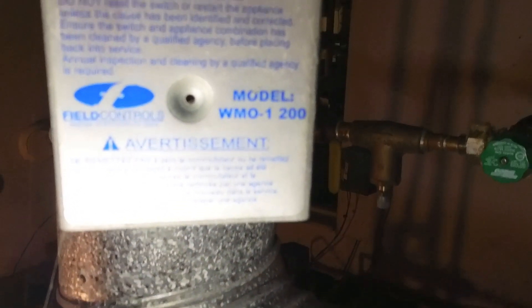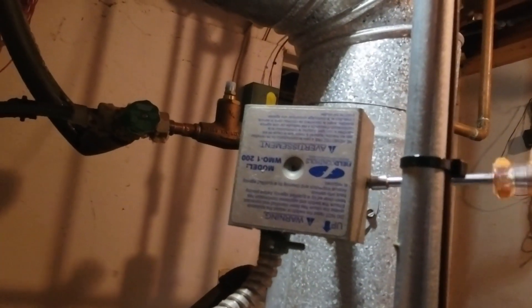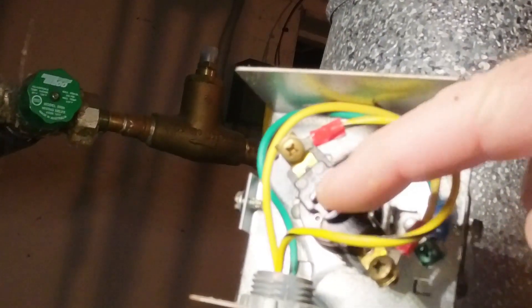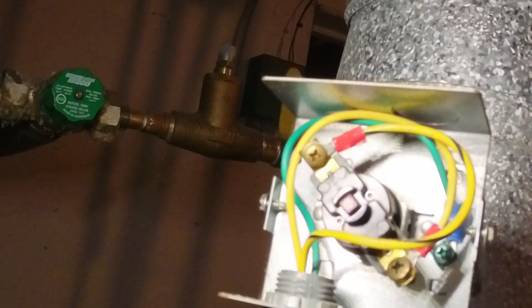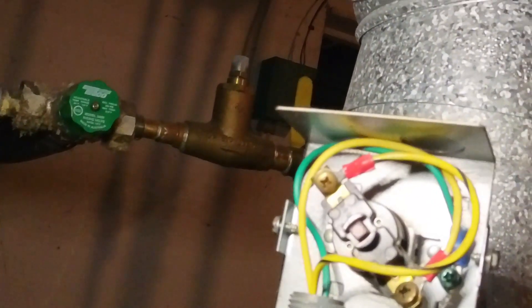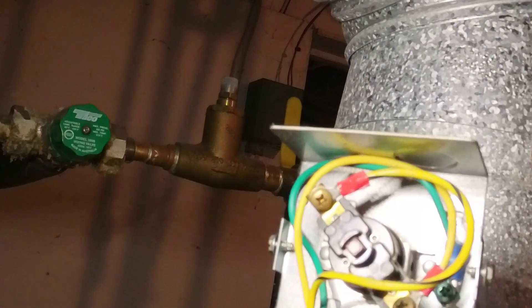In the center there is a high limit switch — if it gets too hot, that's a manual reset; it will trip and you'll have to manually reset it. This is the manual reset here. There is a yellow wire that comes up from the burner, which I'll show you how that's wired later.